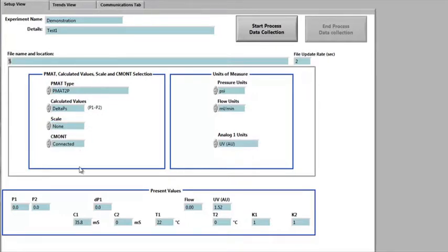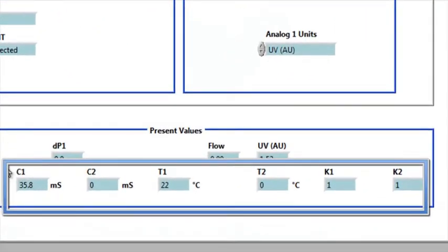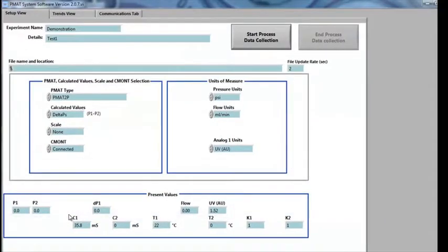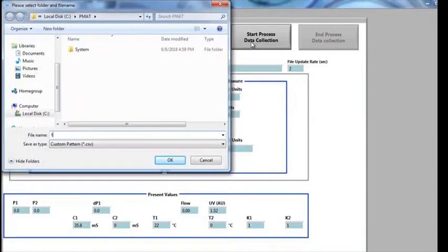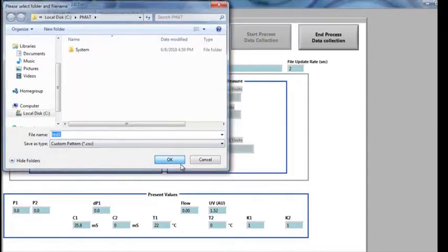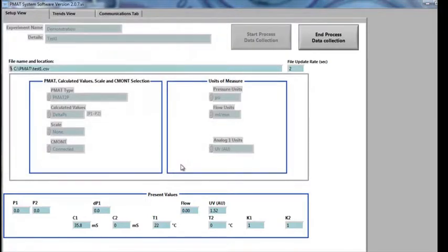Once the CMONT is connected to the computer, it is selected, and then its data readings appear at the bottom of the setup view. The Start Process Data Collection button commences the data logging by naming the file and selecting OK from the standard Windows dialog box. The data file fields become disabled as the data file is now formatted.